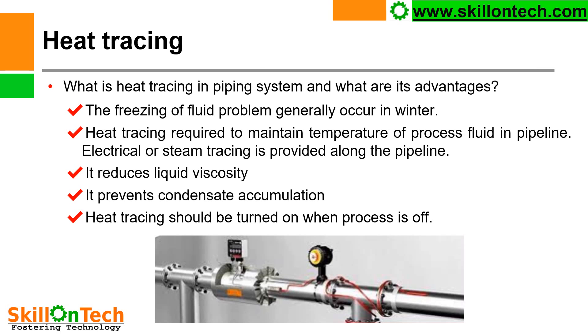Heat tracing. You can see a picture of a pipeline where heat tracing is provided. What is heat tracing in a piping system and what are its advantages? In industries where atmospheric temperature is very low, freezing of fluid in the system is a very common problem. To avoid this freezing problem, which occurs generally in winter, heat tracing is provided. Heat tracing is required to maintain the temperature of process fluid in the pipeline. There are two types: electrical or steam tracing. It reduces liquid viscosity, prevents condensate accumulation. Heat tracing should be turned on when the process is off.